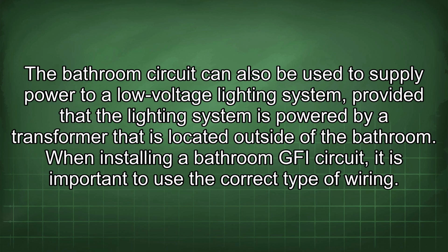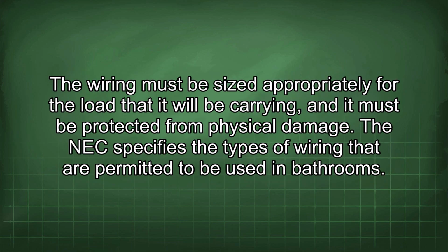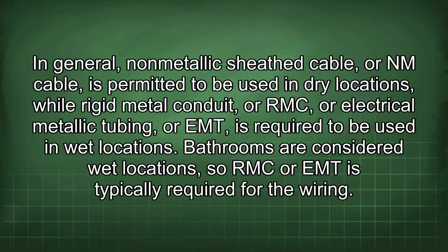When installing a bathroom GFI circuit, it is important to use the correct type of wiring. The wiring must be sized appropriately for the load that it will be carrying, and it must be protected from physical damage. The NEC specifies the types of wiring that are permitted to be used in bathrooms. In general, non-metallic sheathed cable, or NM cable, is permitted to be used in dry locations, while rigid metal conduit, or RMC, or electrical metallic tubing, or EMT, is required to be used in wet locations. Bathrooms are considered wet locations, so RMC or EMT is typically required for the wiring.